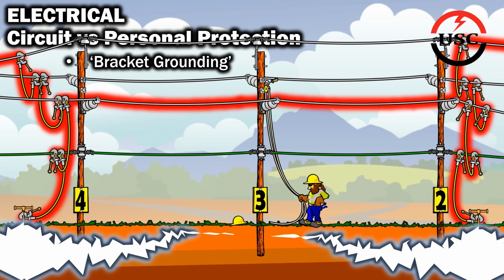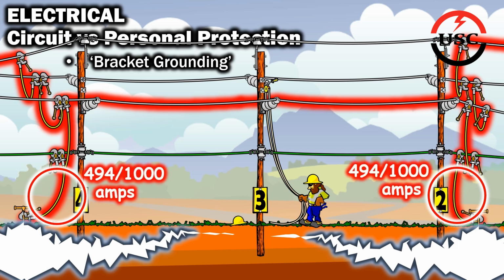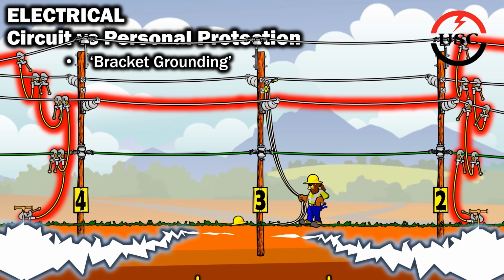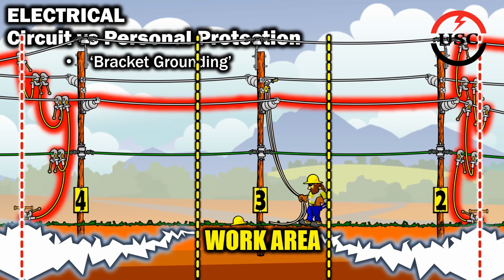This isn't saying that bracket grounding doesn't provide any indirect benefits for workers. Installing multiple sets of grounds provides multiple pathways for the current to travel. This results in the fault current being divided up between the sets. This holds true in the example we covered, where each set respectively channeled 494 amps of the total 1000 amps of fault current. In addition, by having those grounds positioned away from the work area, ground worker exposure to the effects of step potential can be significantly reduced.